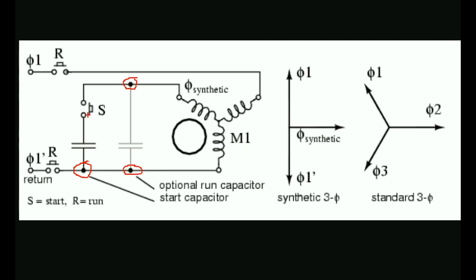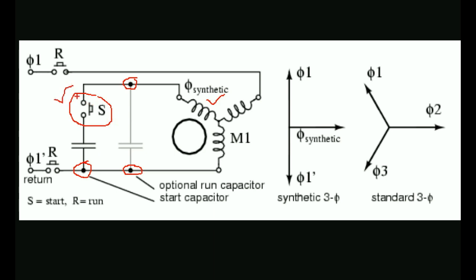Once we connect the additional terminals, if we have a second capacitor and the value of R is changed, this capacitor will be a running capacitor. In an induction motor you have 5 to 7 times high starting current. The value of starting capacitor is 4 to 5 times the running capacitor — for example, if running capacitor is 15μF, the starting capacitor is 60μF.